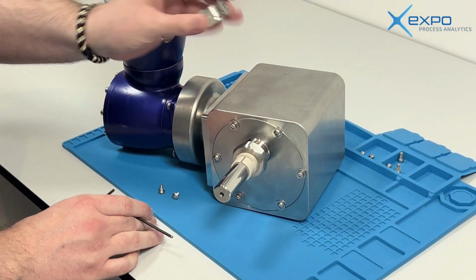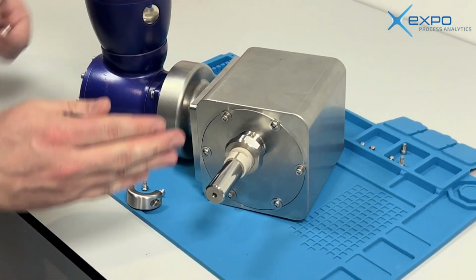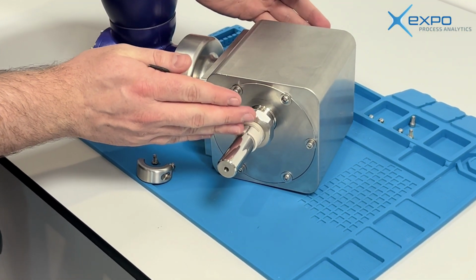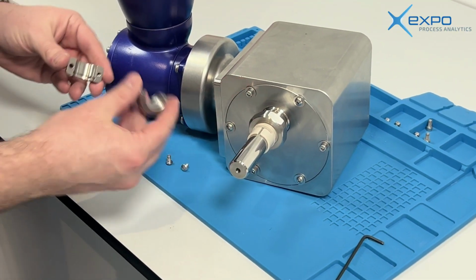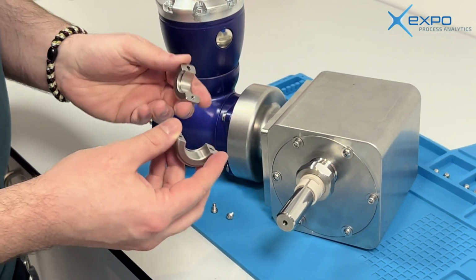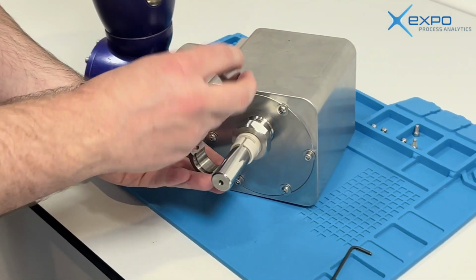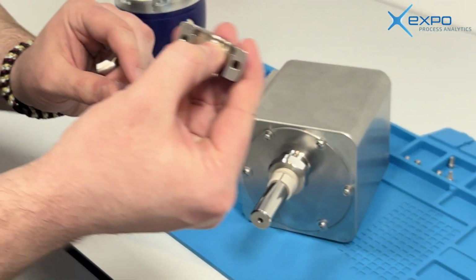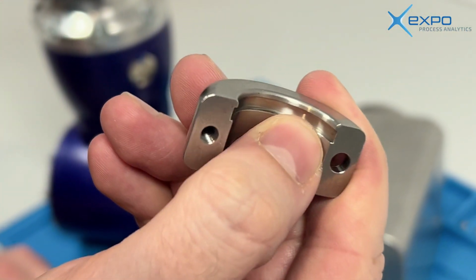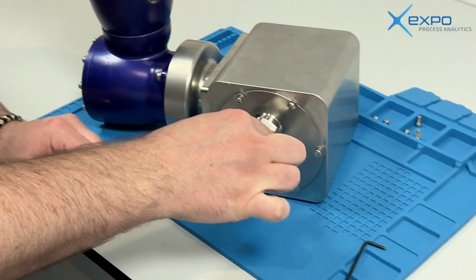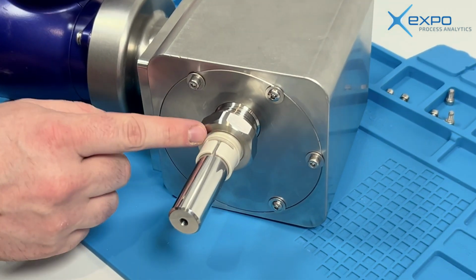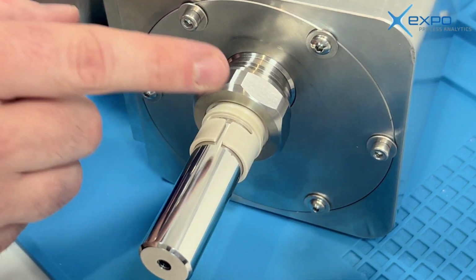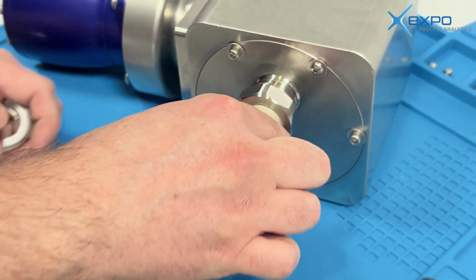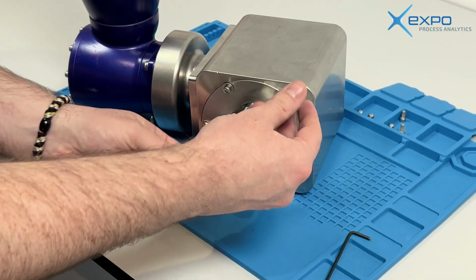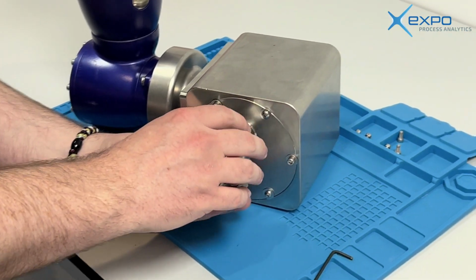So once the stopper has been applied to the front of the device, you know the length that the probe needs to be set to, at which point you'll use the two split clamps. So these get positioned over the back of the compression fitting. You'll see that there's a notch in these clamps that aligns with the shoulder on the compression sleeve, and there's one of these top and bottom.